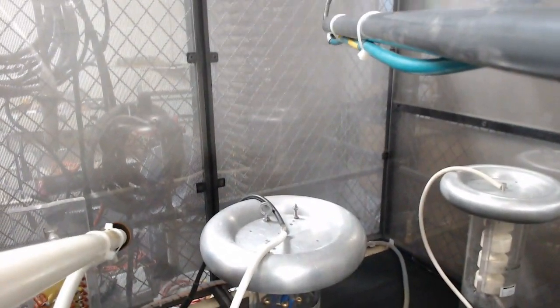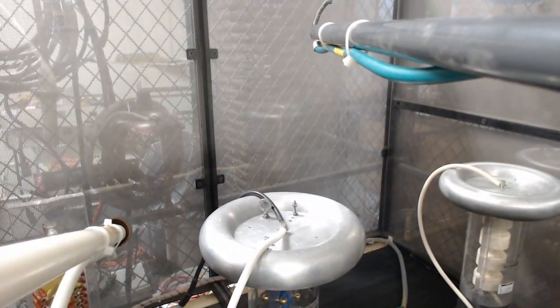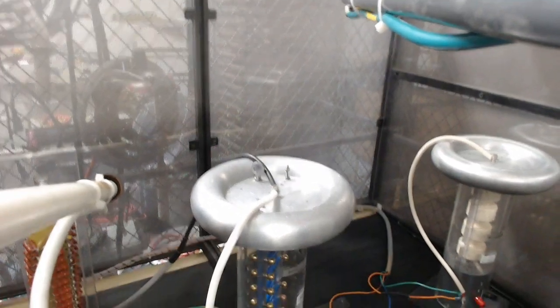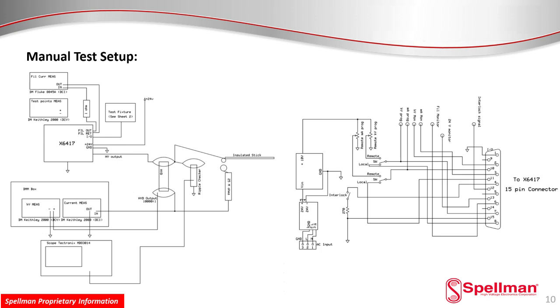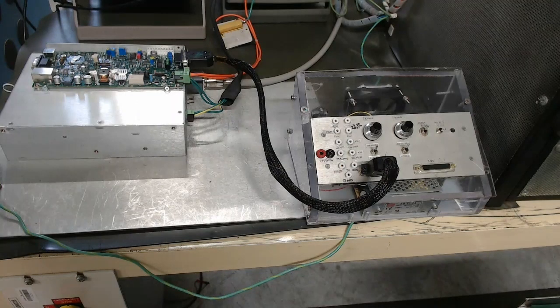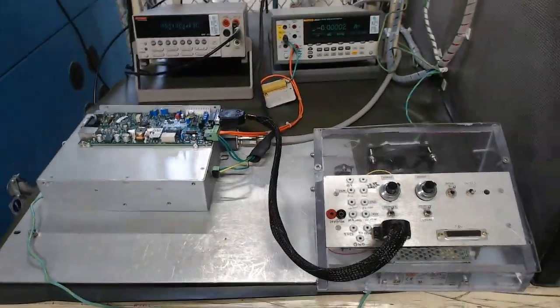After the arc testing has been completed, arc testing passing is recorded in the datasheet and the test setup is configured for the following tests. The test setup now being shown is meant for the manual interface testing, which is done with the help of an analog interface test fixture connected to the 15-pin connector of the X6417. During this test, the test fixture and load are changed in various configurations for testing for accuracy, regulation, and other specified characteristics. As you can notice in the video, the test fixture is connected to the 15-pin connector.